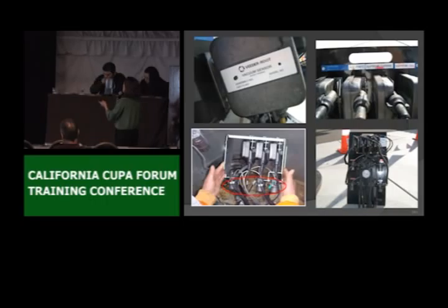So here's a close-up. Here's a typical setup of how you might find them in the sump, a section of 4. And this one has some labels. And what you also find, just looking at these labels, it looks like you can have one sensor per one component. So this label has Sump Fill. This one right here has Sump Turbine. And this one covers all vents. So there's all sorts of combinations you can have. I imagine it depends on the setup of the station, the layout of the piping in the tanks, and the limitations per LG 113.